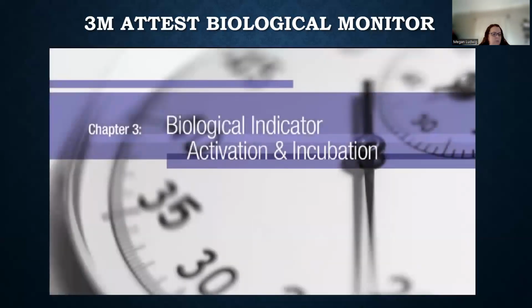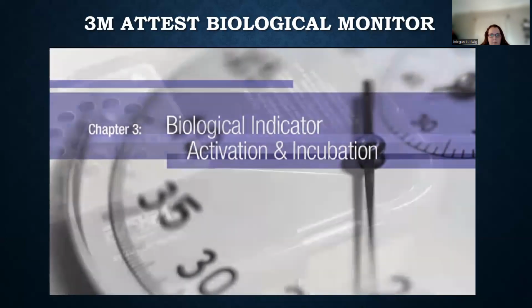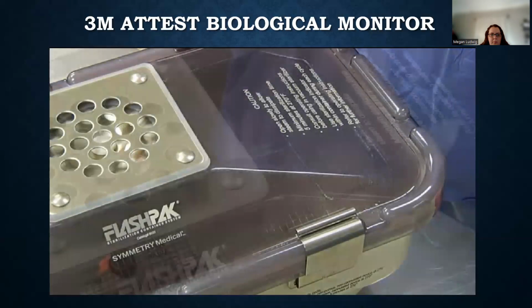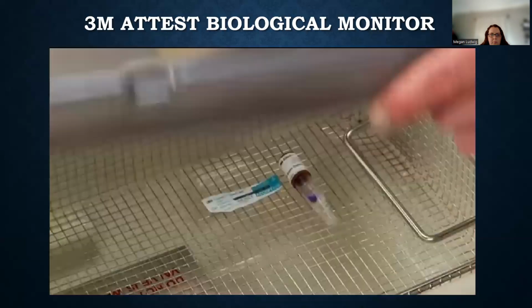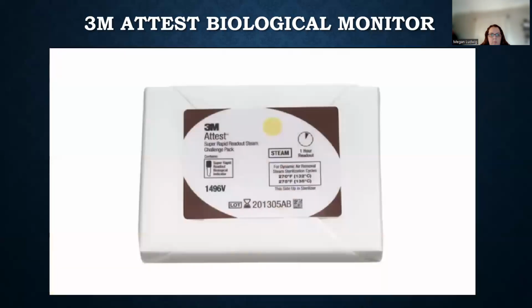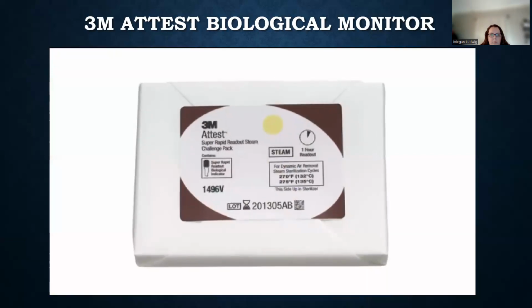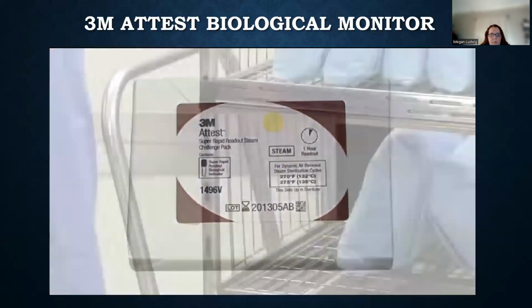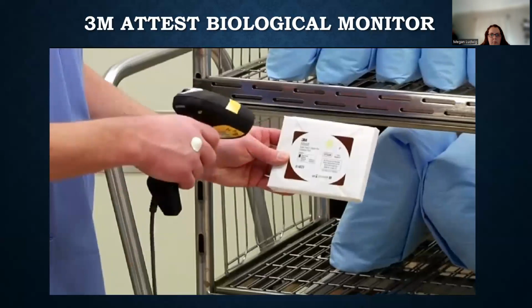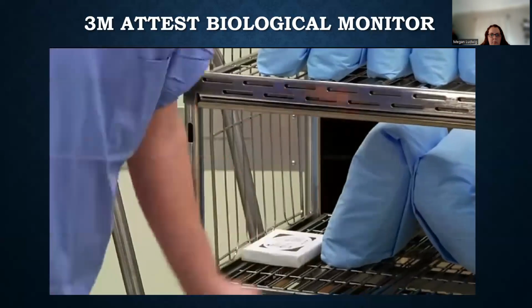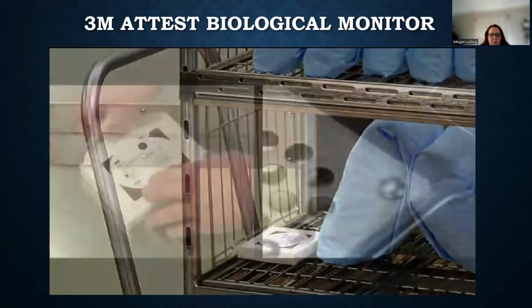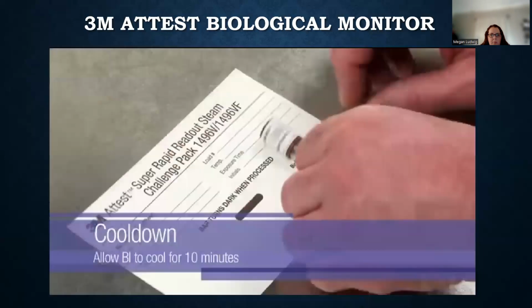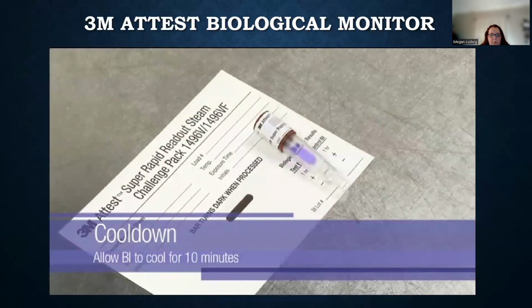Let's look at how to activate and incubate a super rapid BI in the Auto Reader 490. The first step is to remove the BI or challenge pack from the sterilizer. If using an Attest Super Rapid Readout BI challenge pack, if desired, scan the 2D barcode on the label to record product catalog number and lot code. Open the challenge pack and allow the Attest Super Rapid BI to cool for 10 minutes before activating.